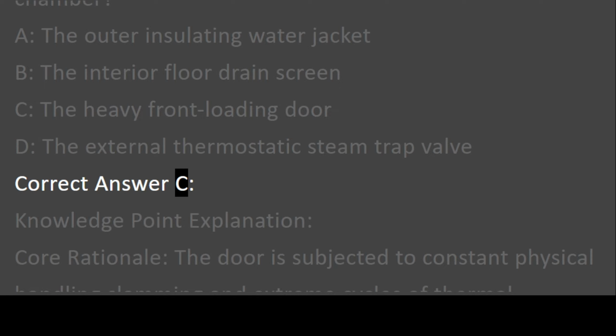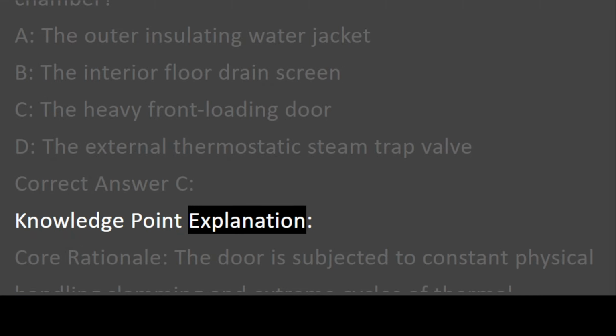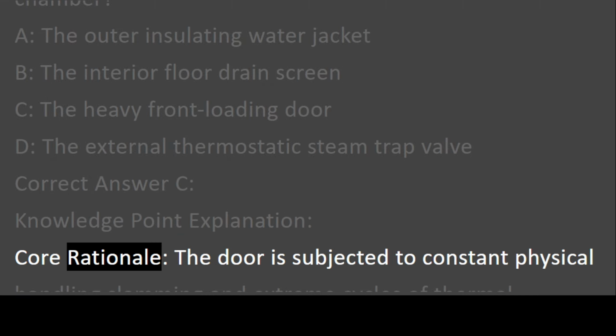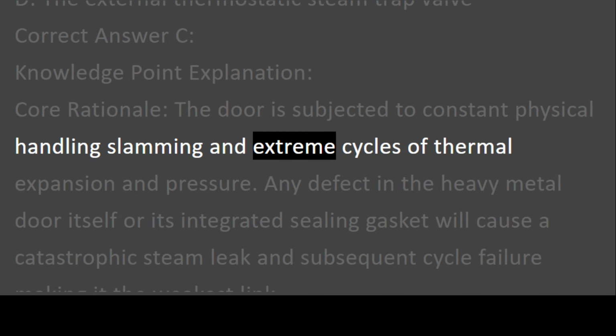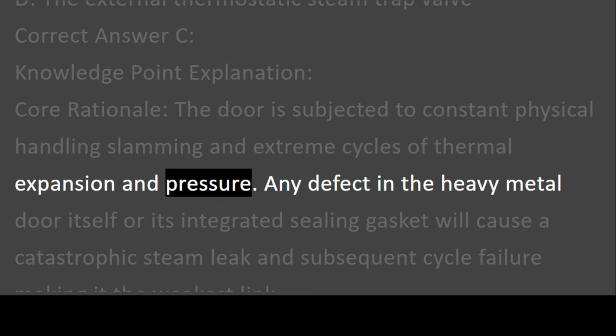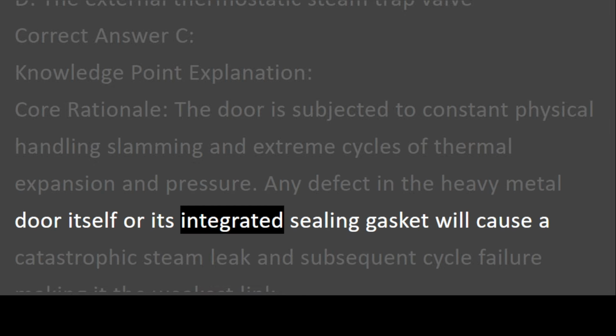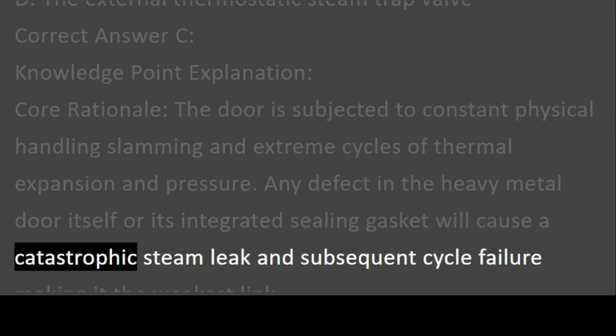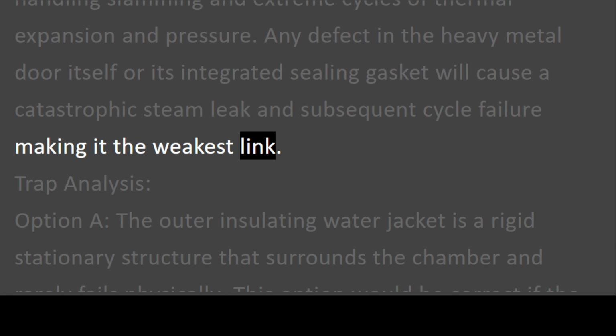Correct answer C. Knowledge point explanation. Core rationale. The door is subjected to constant physical handling, slamming, and extreme cycles of thermal expansion and pressure. Any defect in the heavy metal door itself or its integrated sealing gasket will cause a catastrophic steam leak and subsequent cycle failure, making it the weakest link.